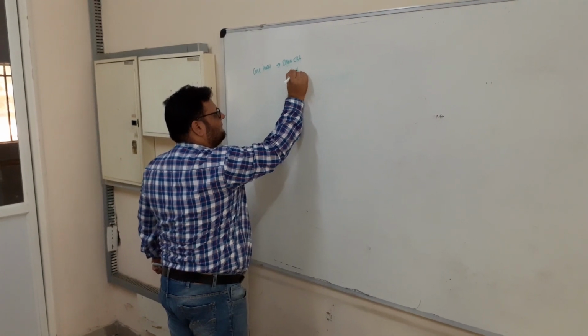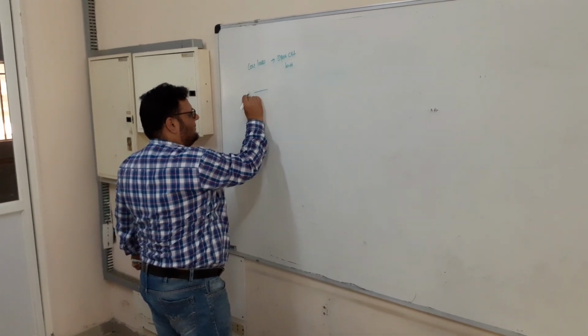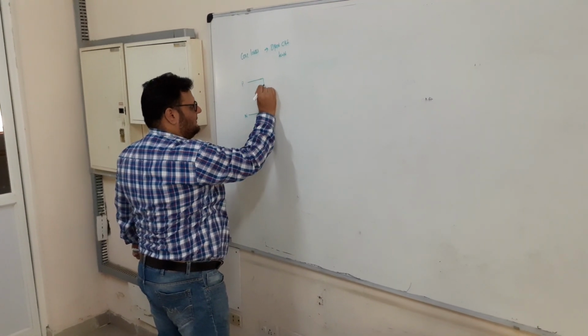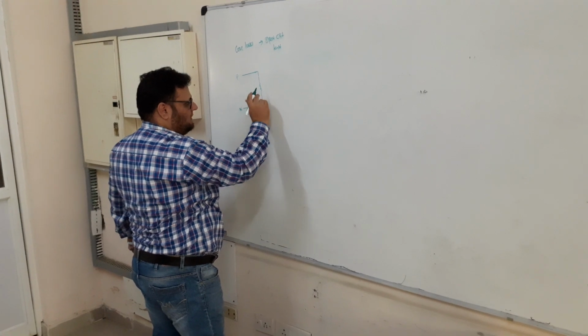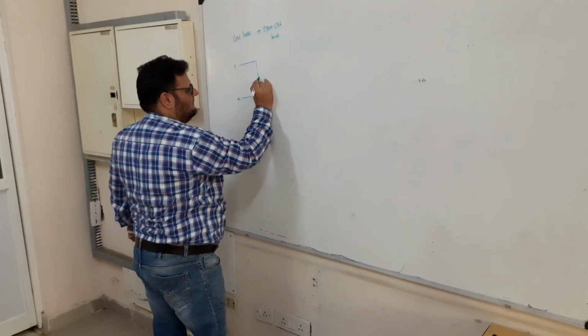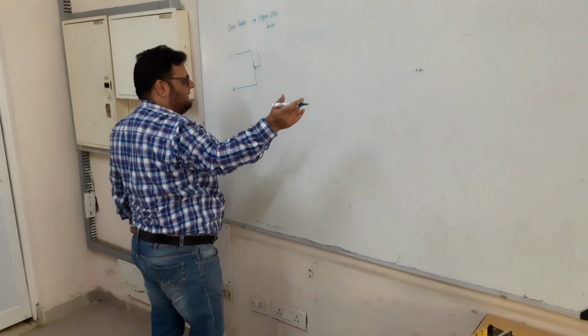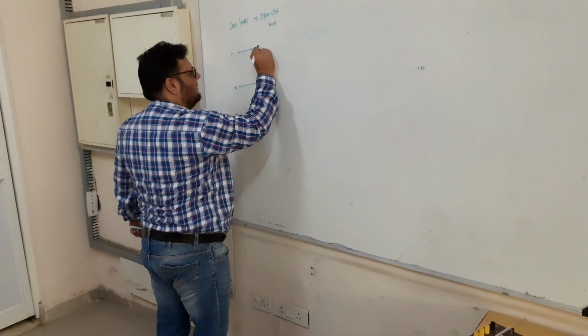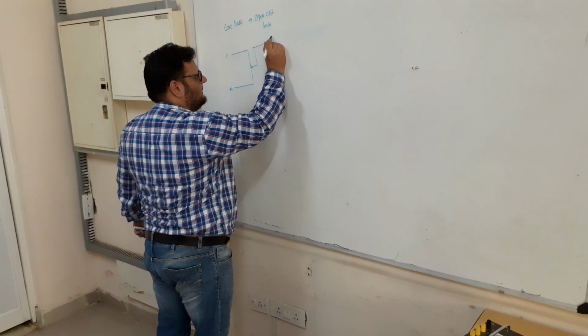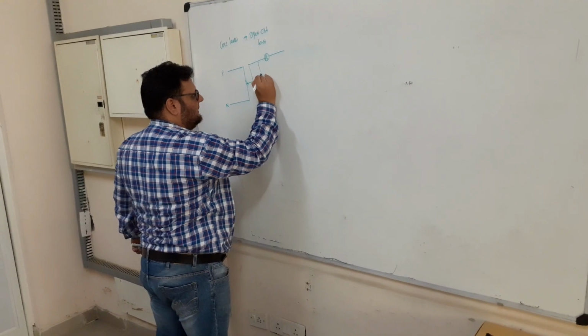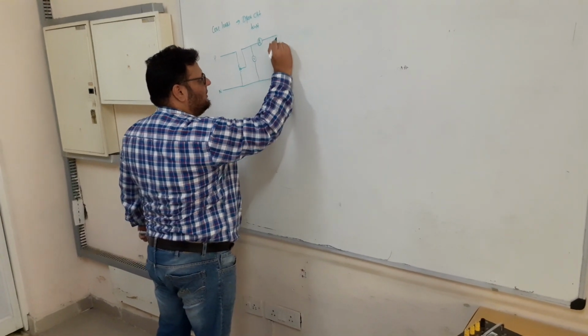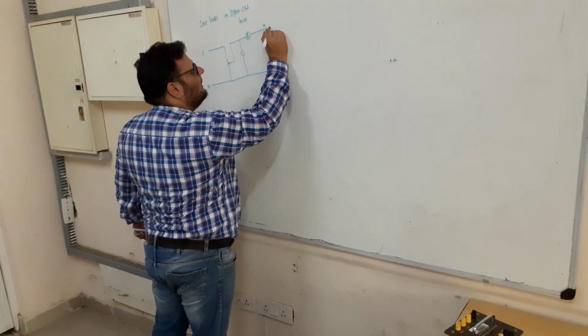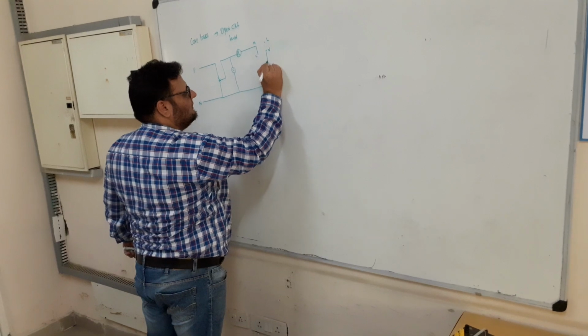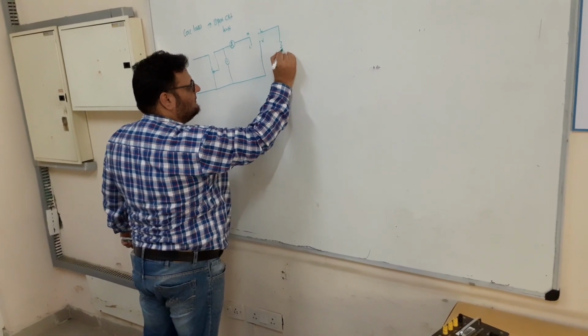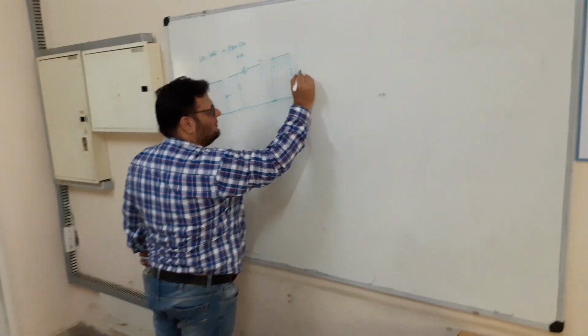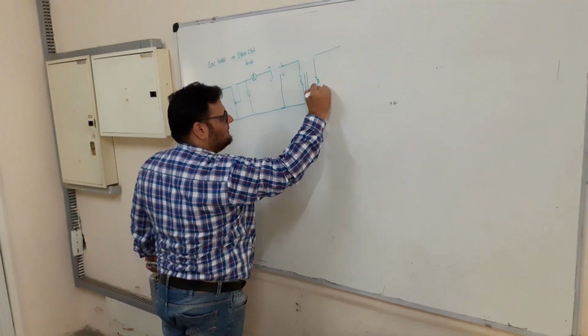So for the open circuit test, if you take any transformer in a lab, you have your phase, you have your neutral, and you will take a variac. Variac is an auto transformer wherein you can vary the voltage from 0 to 270, meaning 20 percent extra it can vary. Here you will be connecting an ammeter, and across this you can connect a voltmeter like this, and you have a wattmeter where the connections are M and C, and this is your L, this is your V. This is the primary side first, and if you have an air core you can represent it like this, and this is your secondary side.